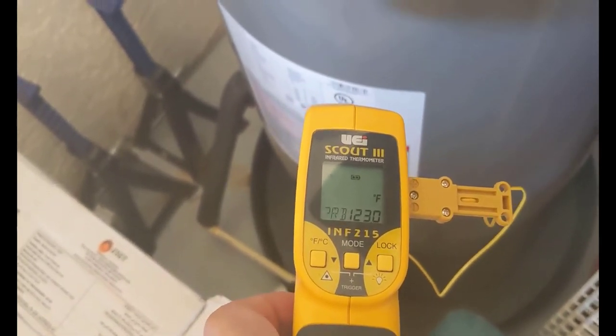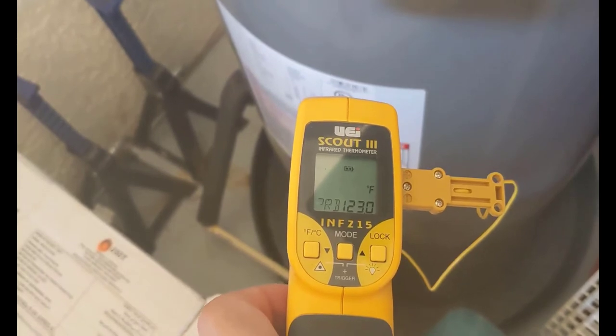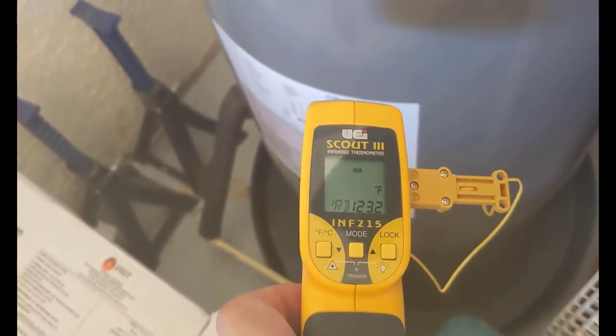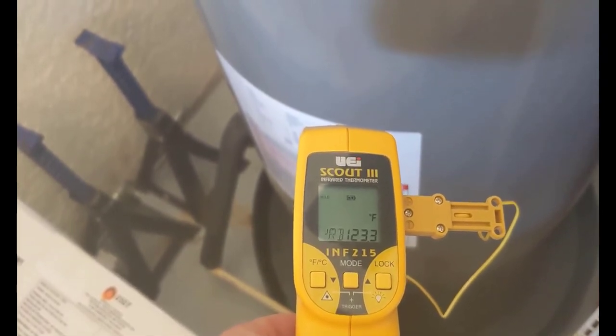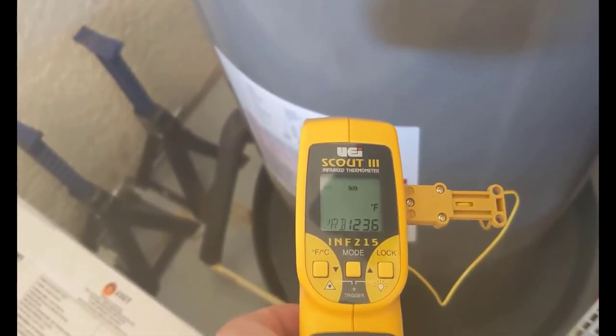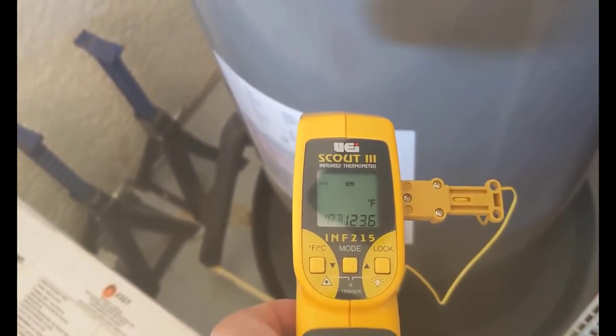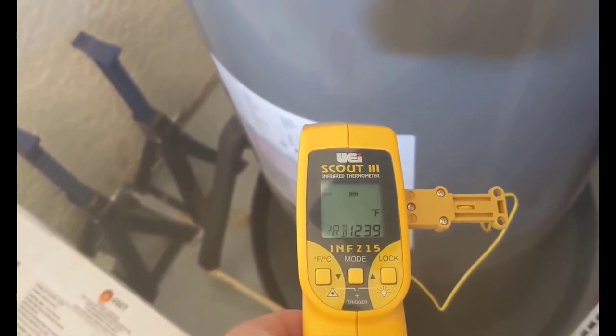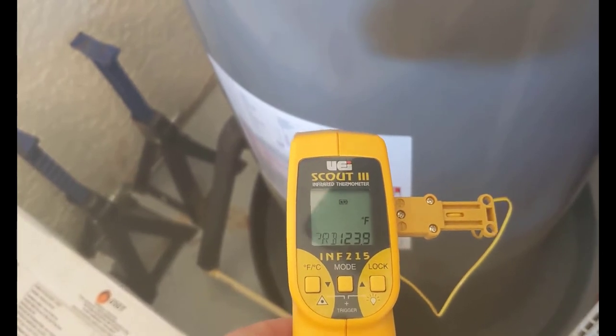So we're easily getting a 30 plus degree rise just by doing something you do all summer long anyway which is cool the house. So as you're running the air conditioning inside the house, the heat exchanger is taking the heat from that wasted heat from the air conditioner and using it to heat your water. So right now we're getting 30 degree plus rise easily.